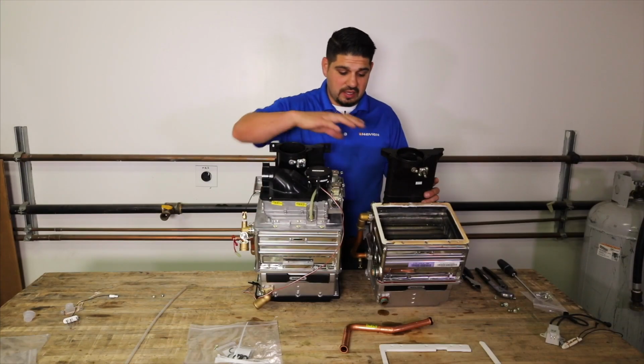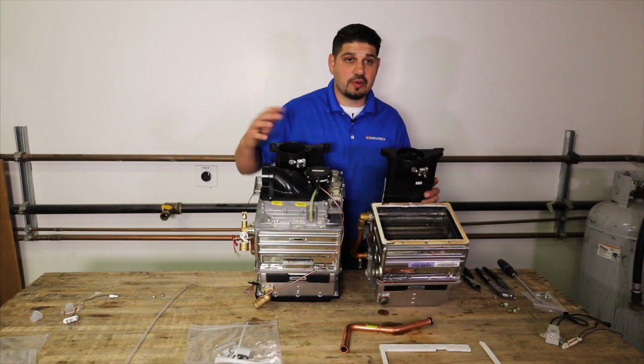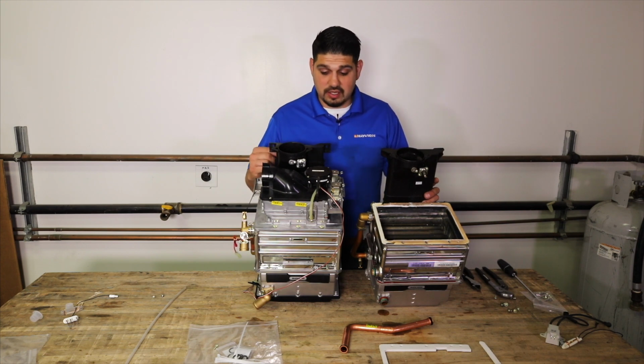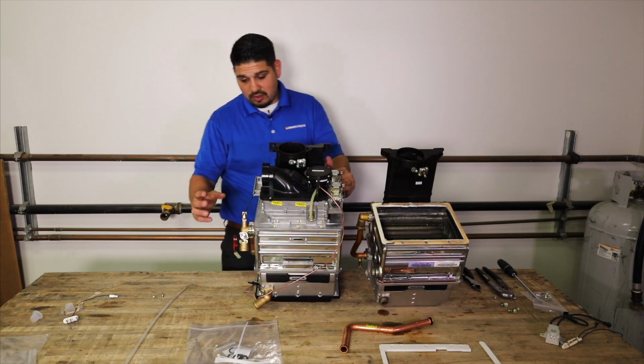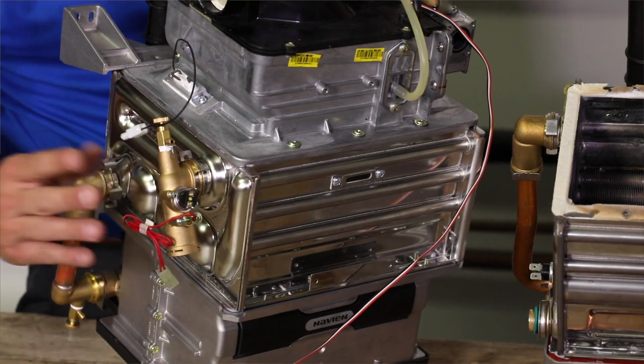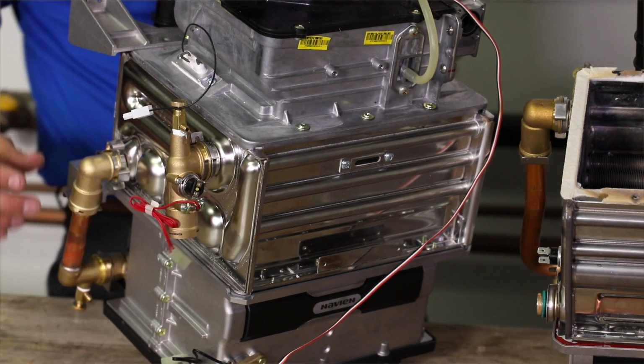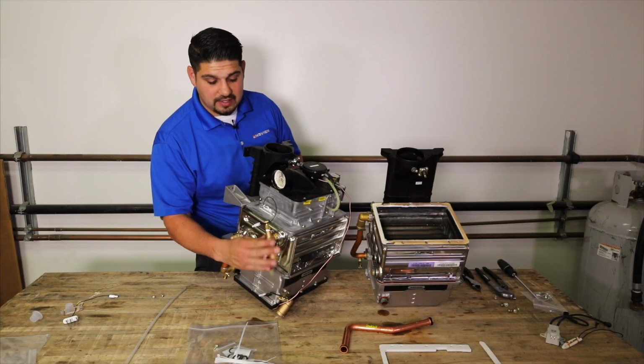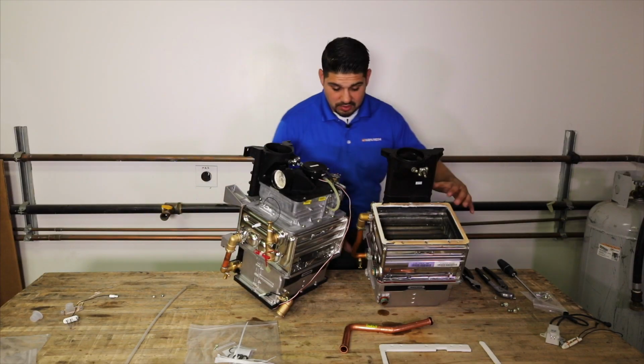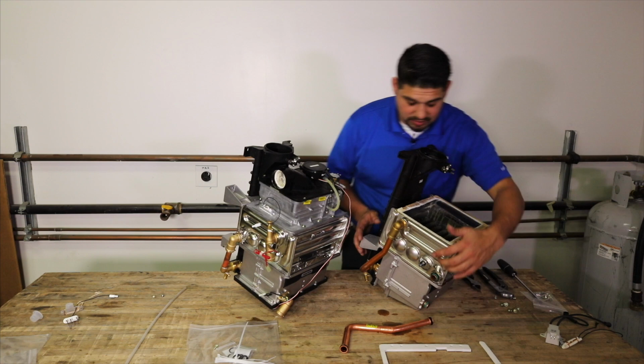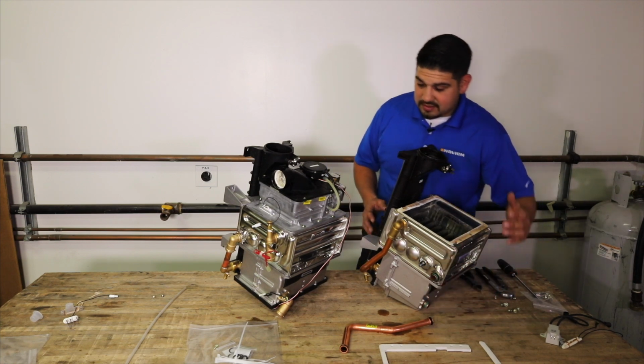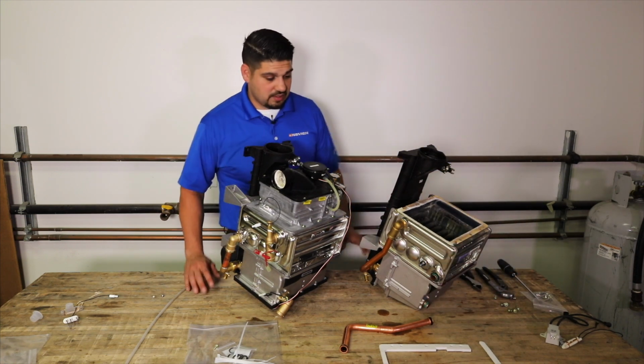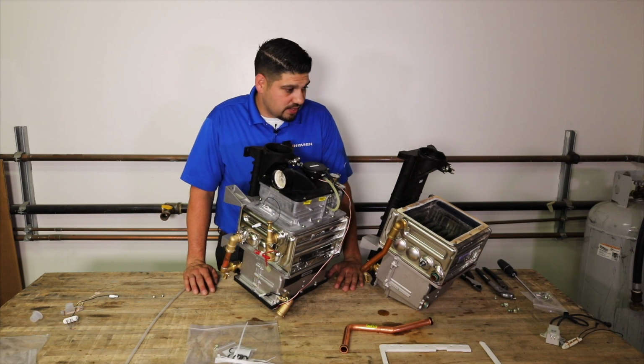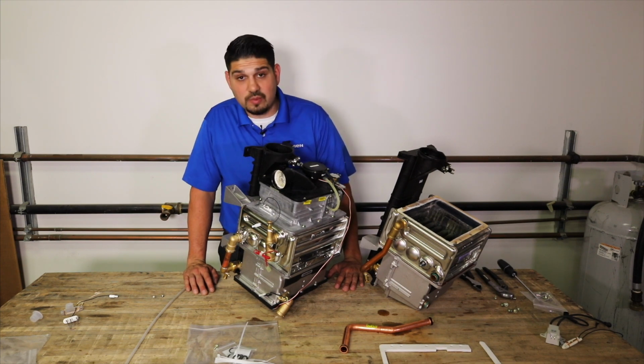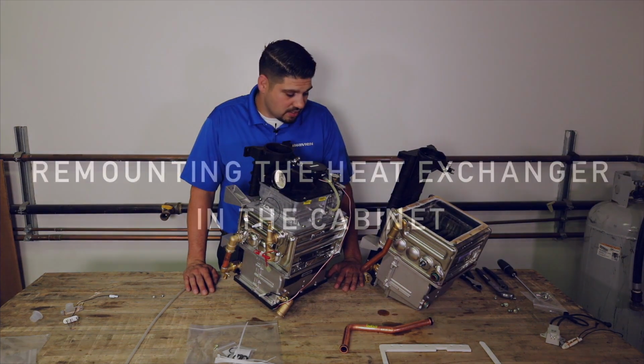Now that we've completely switched over our burner to our new heat exchanger, there's a couple things I want you to take note of. On our new heat exchanger, the high limit switch has been relocated. So now it's on this outlet elbow, and on the other unit, or your older heat exchanger, it was right here on the side. So it's a little bit of a change. That's about all we're really going to see here, but I just wanted to bring that to your attention.